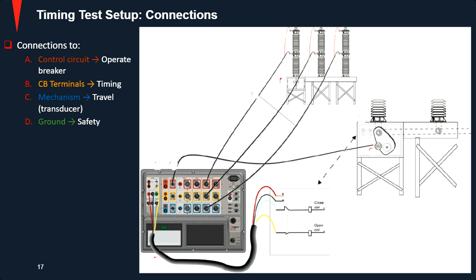So you start off with your control circuit. This is what's going to actually give the command to the breaker from your test set to either open or close, based off the close coil and open coil or trip coil. Once you have those connected, the next thing you're going to want to connect will be your terminal leads. This is what's going to sense when those breakers open and close based off the continuity check of those instruments. So you put a small voltage on one of the leads, and once that voltage or current is allowed to continue back to the test set, it stops the time.